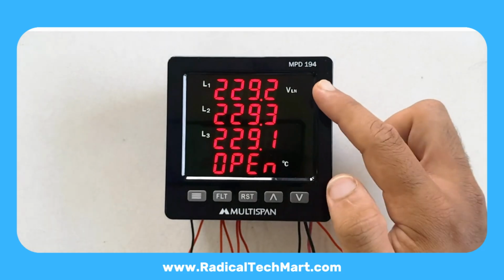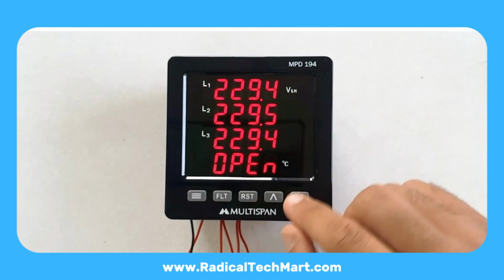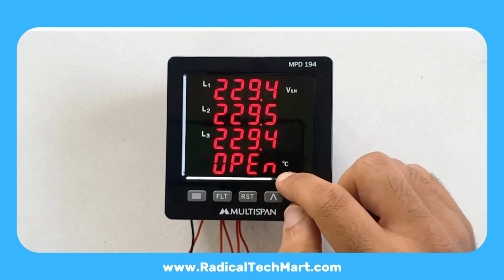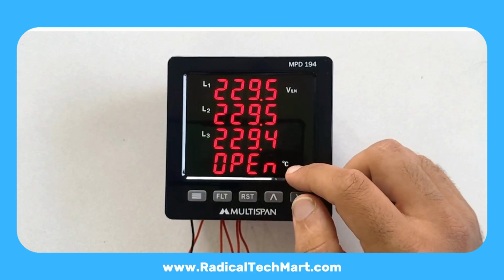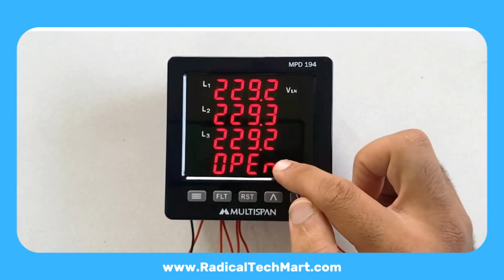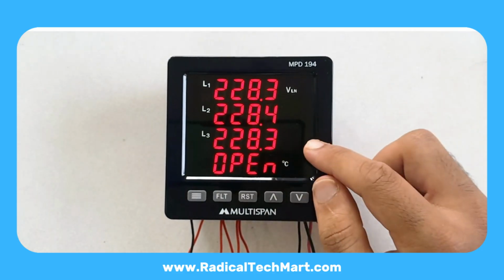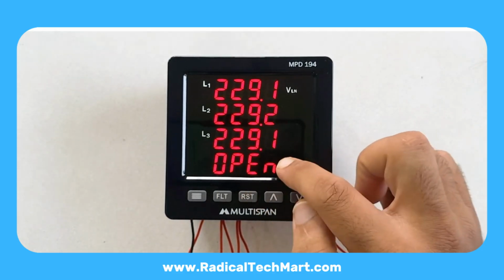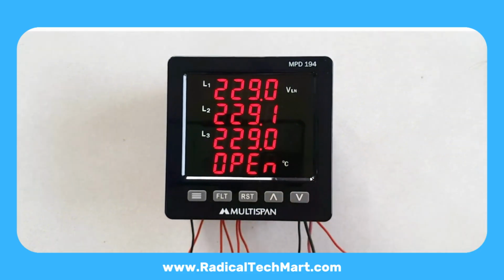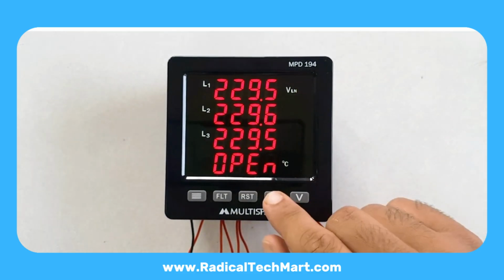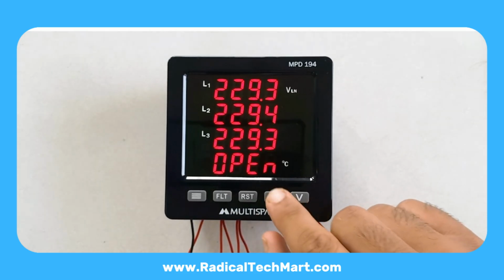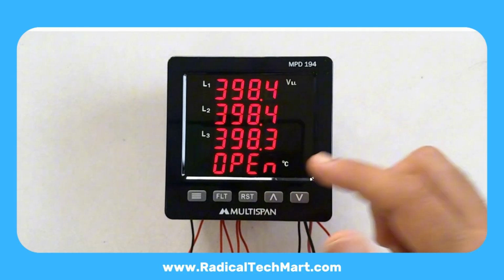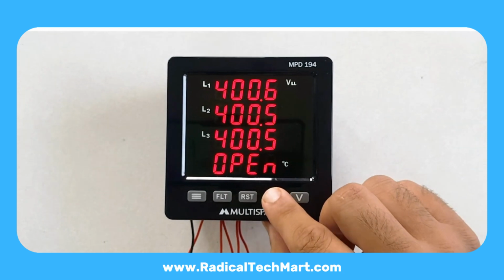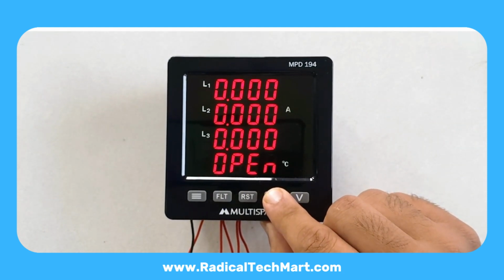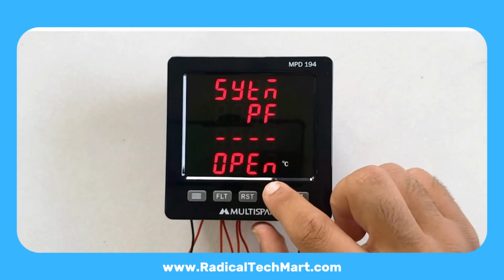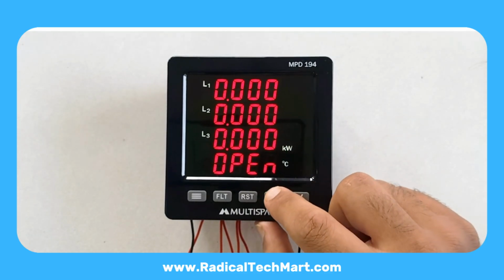Viewing parameters on display. On the main screen, first page, line to neutral voltage. Below, you may see the open message for PTC because we haven't connected a PTC yet. With a healthy PTC, it will show healthy. In trip condition, it will show temperature trip. By pressing the up arrow, you can scroll through all parameters. Line-to-line voltages. Phase currents. Frequency. System power factor. Kilowatt per phase.